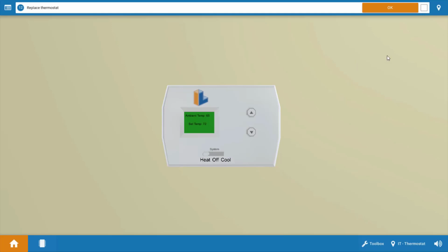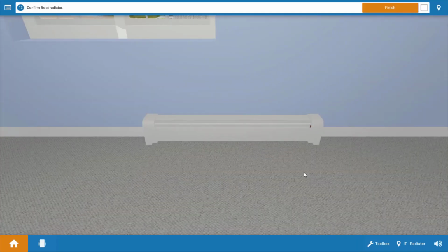Now, the last thing you're going to want to do is watch one full cycle of operation and go up to the residence and make sure that heat is being received in the residence. And if we look at the graphic coming from this piece of baseboard radiation, we can see that, in fact, we do have heat coming into the space.